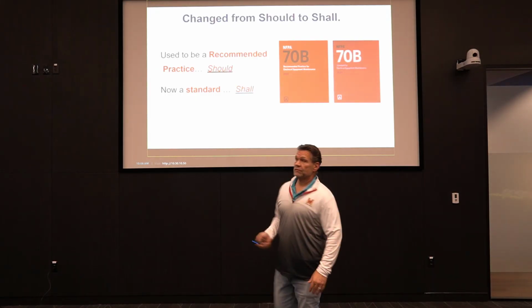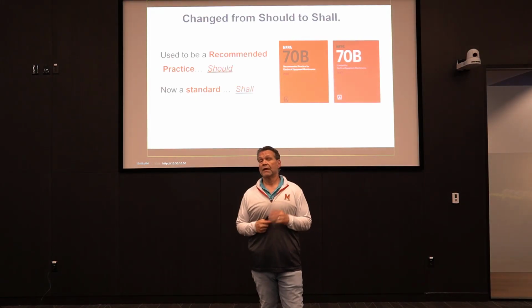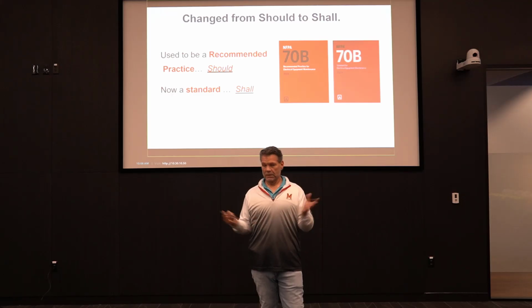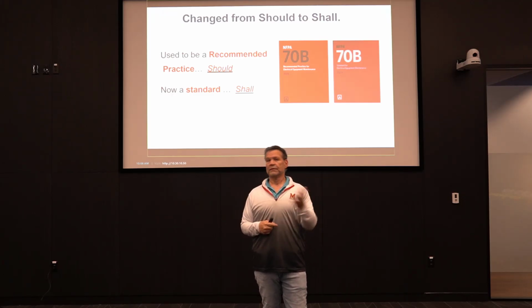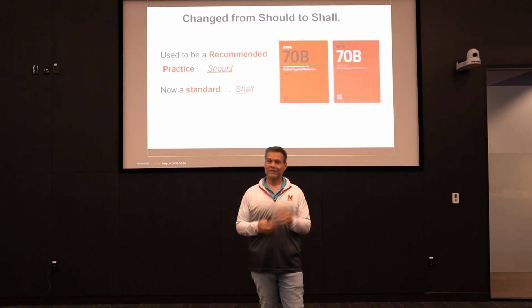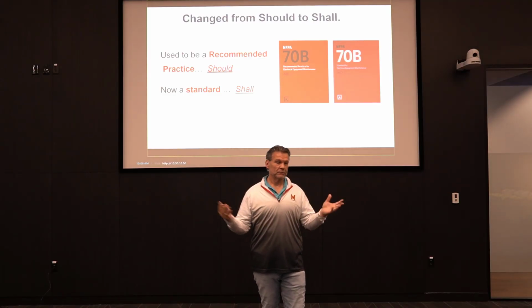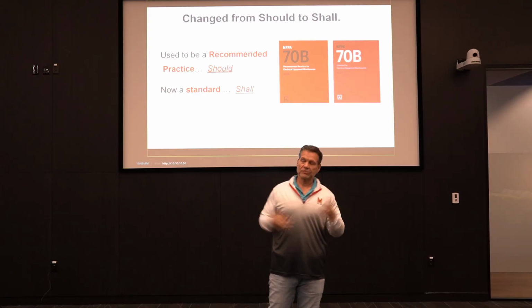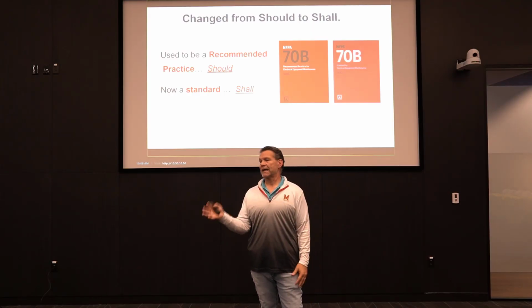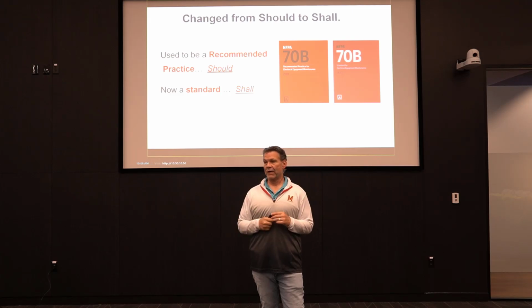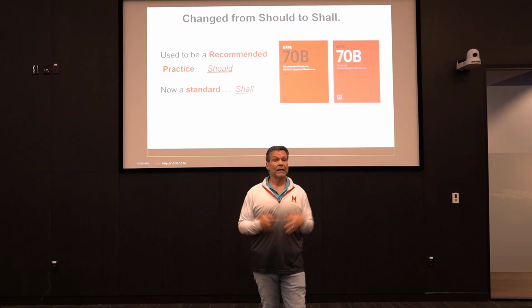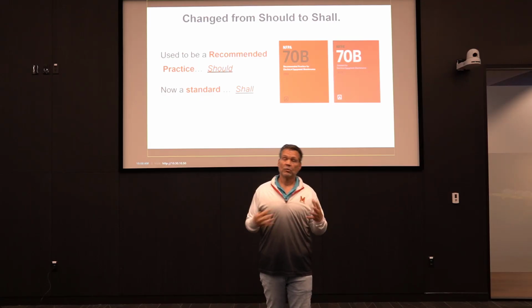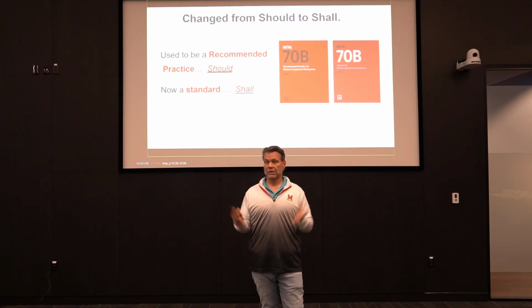So one of the changes for 2023 was NFPA 70B is now a standard. So it went from should to shall. Now, most of my electricians, we deal with the National Electric Code, so we understand should and shall is all throughout the National Electric Code. Should is, that's a good idea. It's a good practice. Shall means it now has to be done. And that's what happened with NFPA 70B. It became a shall, it became a standard, which means that OSHA can now use it to enforce it.